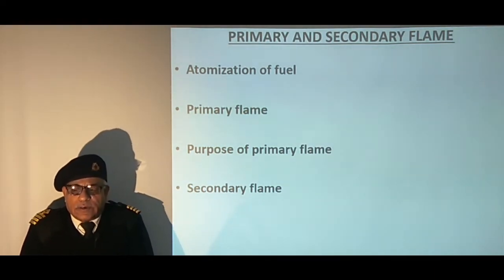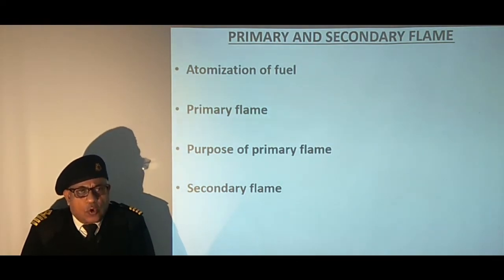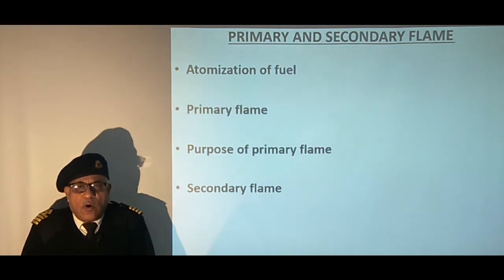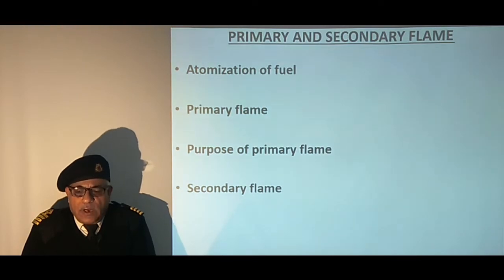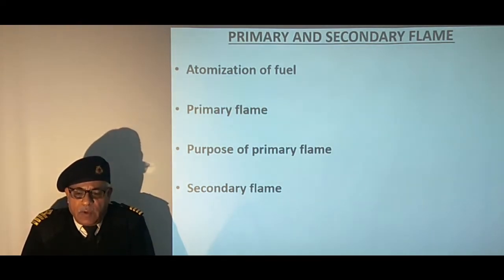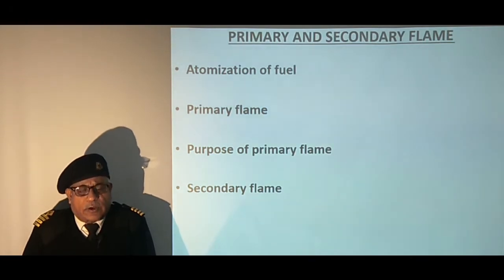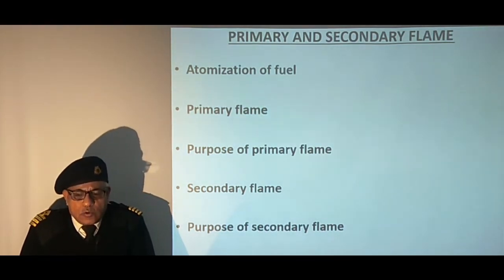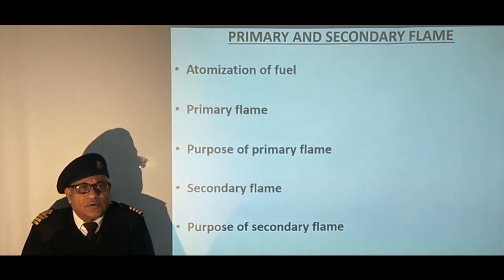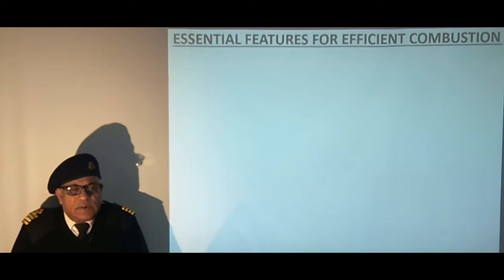The larger oil droplets get heated while passing through the primary flame zone, vaporize, and begin to burn to form the secondary flame. The vanes of the swirlers provide the required flow pattern to the secondary air. It is essential that the air is steadily supplied and arranged to mix thoroughly with burning particles of oil. For the stability of the suspended secondary flame, the forward velocity of air and oil particles should not exceed the speed of flame propagation. Secondary flame gives heat to the surrounding furnace for generation of steam.